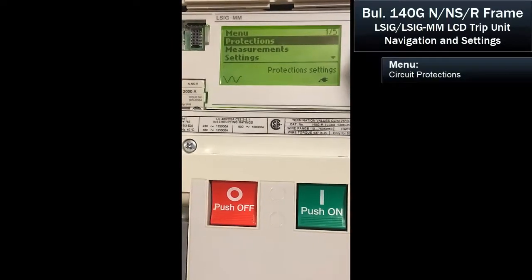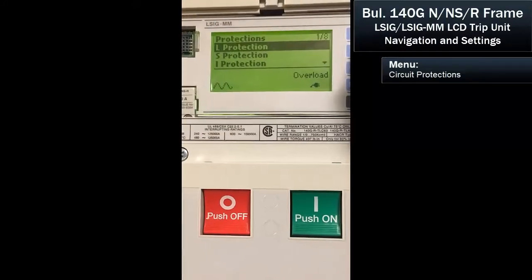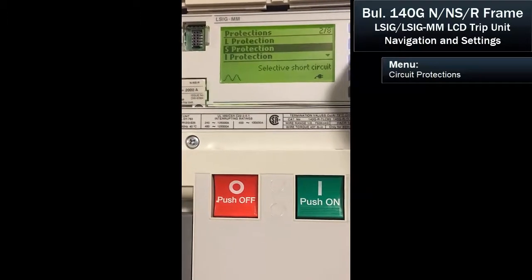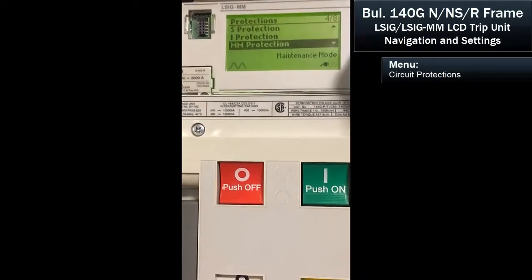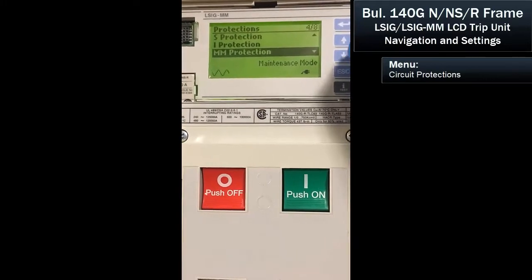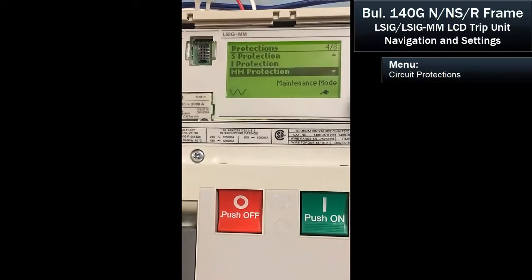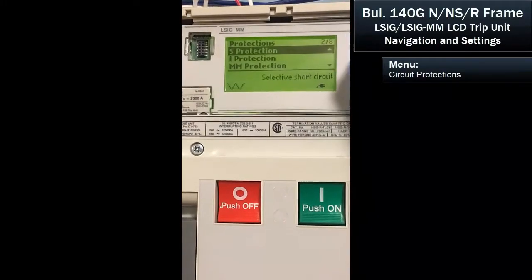Hit the enter key. Just like most breakers, it's going to have long, short, and instantaneous protection. And if you have maintenance mode on the breaker, you'll be able to enable that and set the value. So let's go through typically how we set the standard breaker.